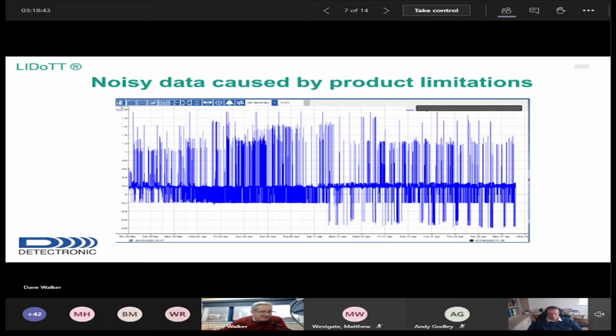But this is now down to the users and the people taking the instrumentation and deploying it into their networks. So this is from a particular live site in the UK, one of the UK water companies. I'm not going to name which one it is. And this is noisy data, as you can see. That dark blue line in the center there is the actual true data. All this is what we call noise. And again, I reiterate, not electrical noise. This is an ultrasonic level sensor, and I'm going to go on to that in a bit. It's where we're losing echo and it's giving wrong data. So this is incorrect data.